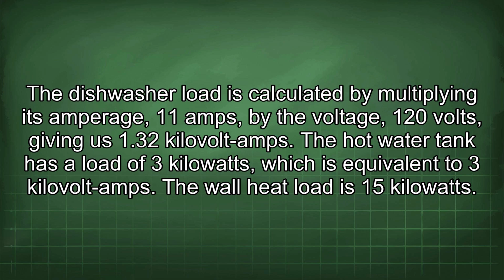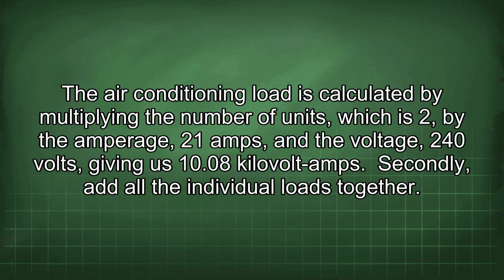The wall heat load is 15 kilowatts. The air conditioning load is calculated by multiplying the number of units, which is 2, by the amperage, 21 amps, and the voltage, 240 volts, giving us 10.08 kVA. Secondly, add all the individual loads together.